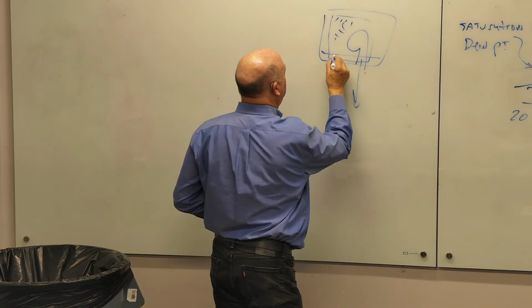Swamp cooler is a pejorative term relating to how they start to smell if you haven't taken proper care of them. So, a swamp cooler is kind of like that saturation lab box I was talking about. You set it up, typically you've got a box, you got a fan that's usually blowing down, but it could also be a side discharge if you want. You've got probably on 3 sides of this thing pads, about this thick, woven fiber, heavy fiberglass. And you've got a sump in the bottom, you've got a little condensate pump that takes the water in the sump and has the little black polypropylene hose just like you see people using in drip sprinkler systems. And it's dripping water all across the top of the pad so that the pad's fully wet.